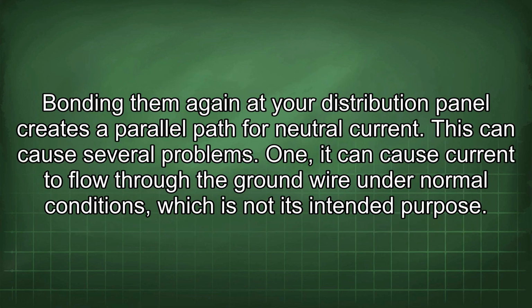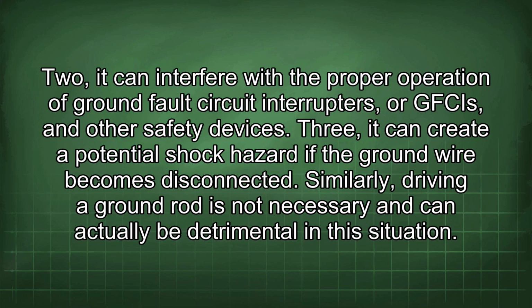Bonding them again at your distribution panel creates a parallel path for neutral current. This can cause several problems. 1. It can cause current to flow through the ground wire under normal conditions, which is not its intended purpose. 2. It can interfere with the proper operation of ground fault circuit interrupters, or GFCIs, and other safety devices. 3. It can create a potential shock hazard if the ground wire becomes disconnected.